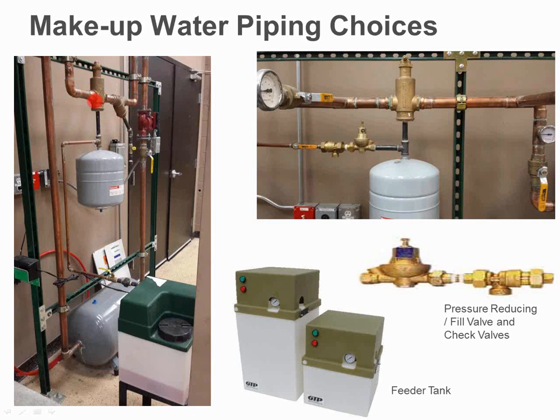Nice convenient thing I like to do is come right off the bottom of that air eliminator because it has a 1/2-inch tapping right down into the expansion tank with a small T. It makes the system very, very simple. That fresh water is that line coming in, and on this one we're using a little glycol feeder, but that line coming in, if that has any air in it, what's the first thing it sees? It sees the air eliminator. So we're trying to get it out right then, right there, before it even gets into the piping system.